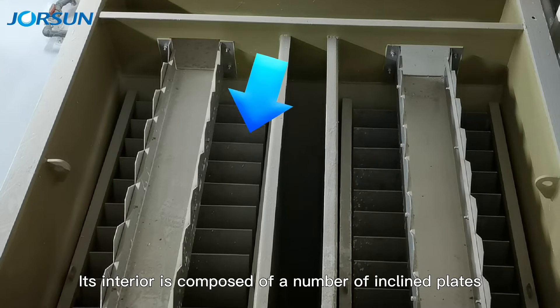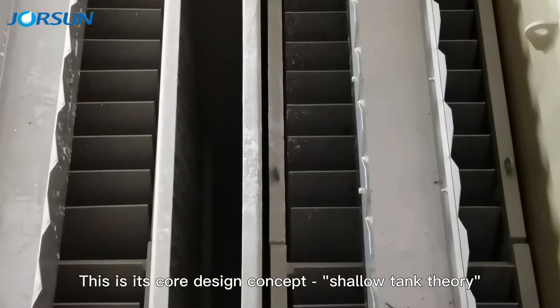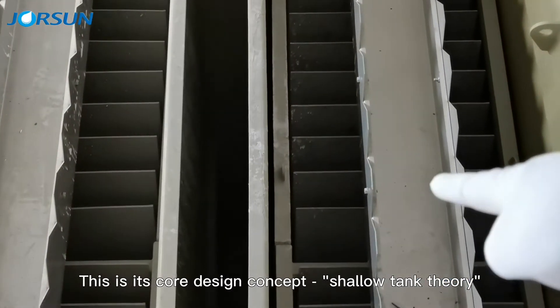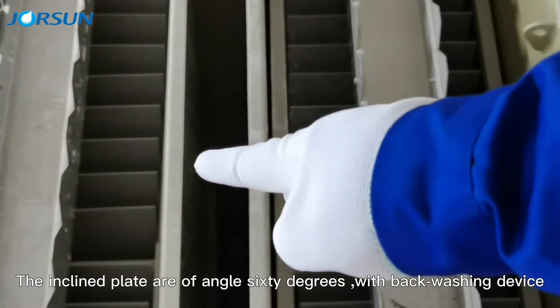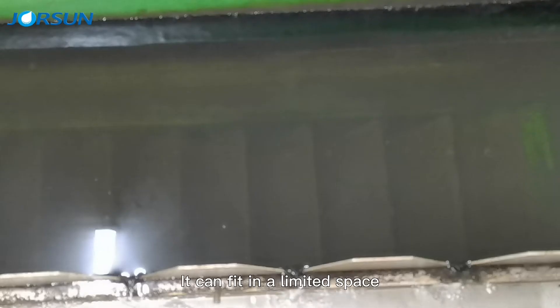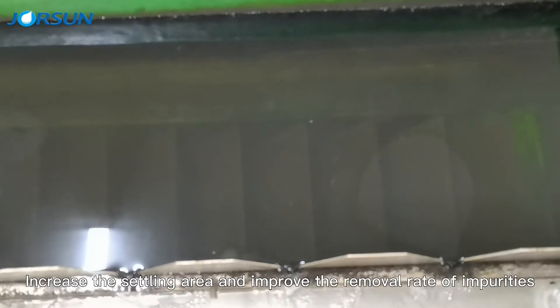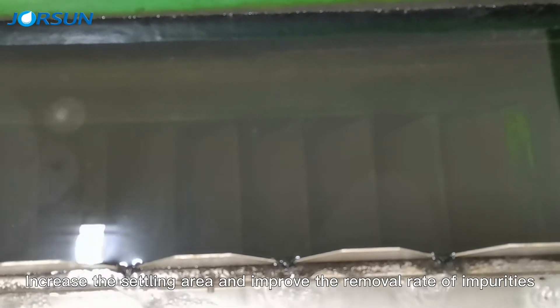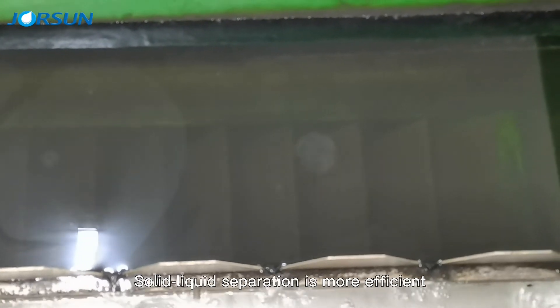Its interior is composed of a number of inclined plates. This is its core design concept: shallow tank theory. The inclined plates are at an angle of 60 degrees. It can fit in a limited space, increase the settling area, and improve the removal rate of impurities. Solid-liquid separation is more efficient.